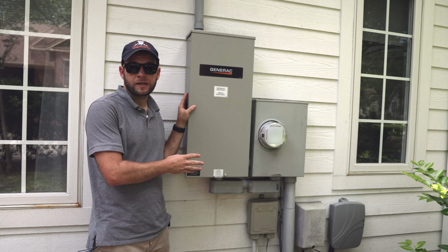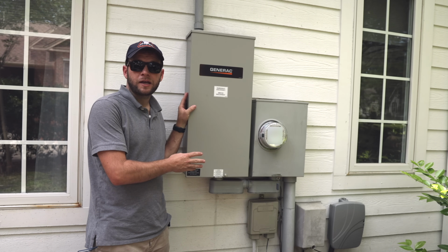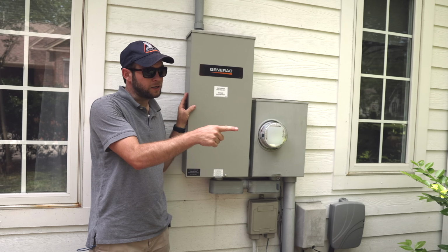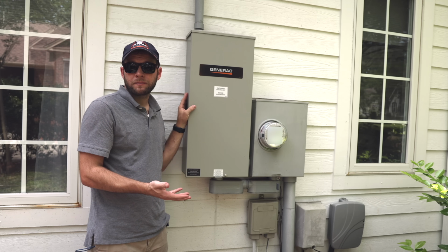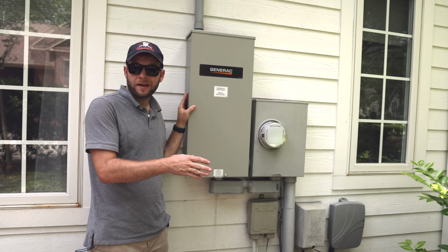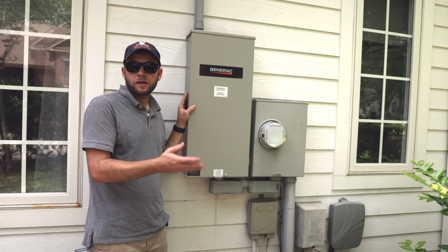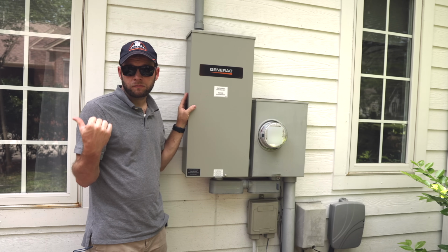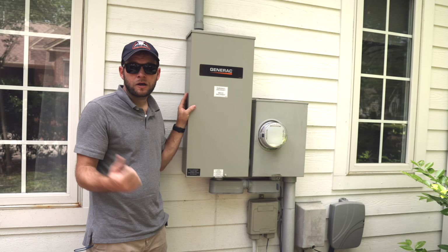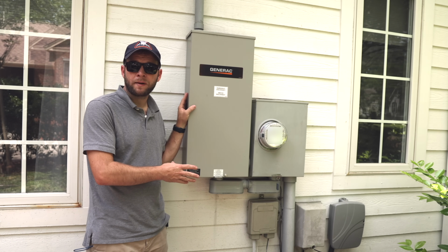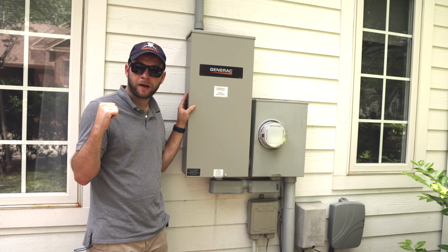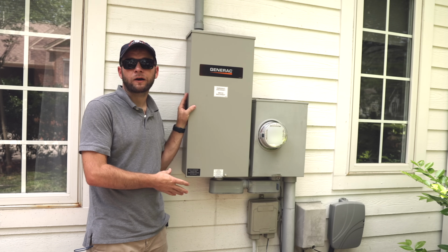Now, the reason that you open this contactor and that it has to make sure that the connection is in fact severed is so that the generator is not feeding back power through the meter into the grid. As if a lineman were working on something, or out at the street working on what they think is a dead power line, they could end up getting electrocuted by your generator, which has essentially become its own little power plant. So they sever the connection to make sure that no power can be fed out to the street, and then they send the power into your electric panel, all automatically without you knowing anything.